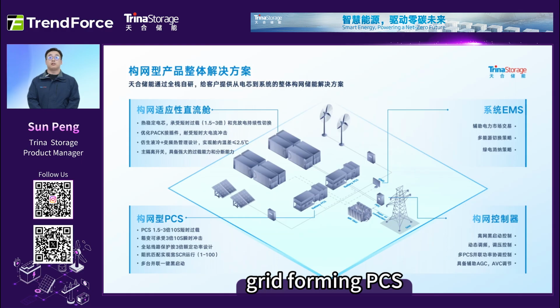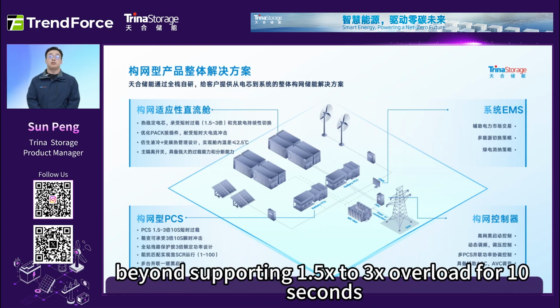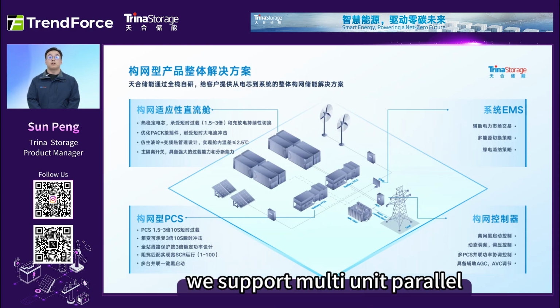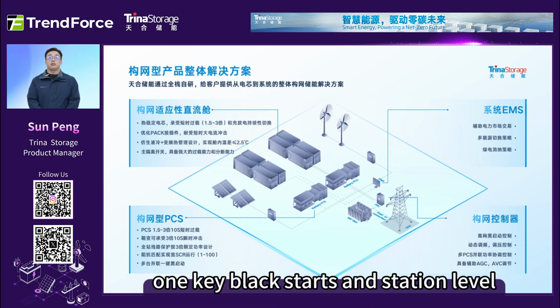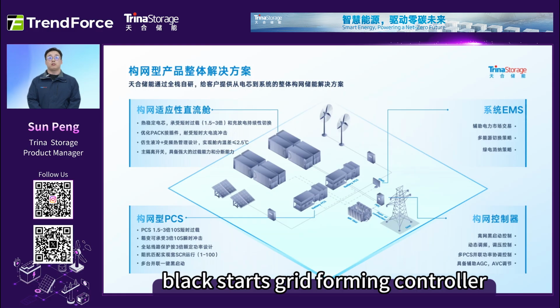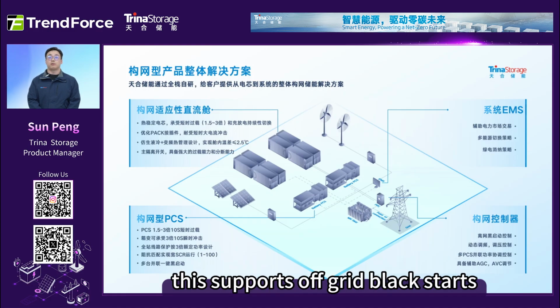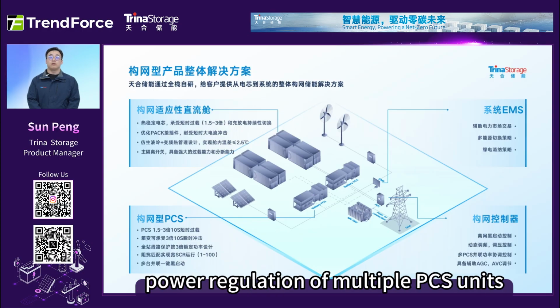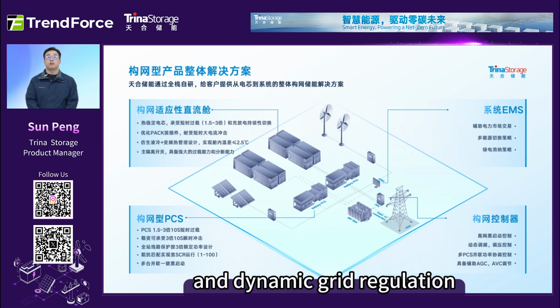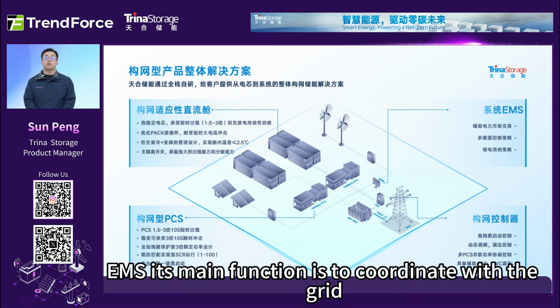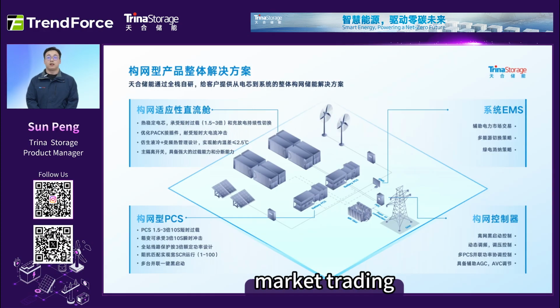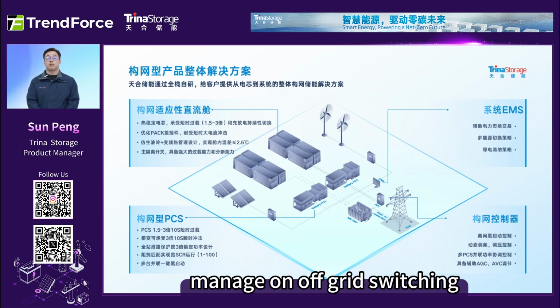Grid forming PCS: beyond supporting 1.5x to 3x overload for 10 seconds, we support multi-unit parallel 1-key black starts and station-level black starts. Grid forming controller: this supports off-grid black starts, power regulation of multiple PCS units, and dynamic grid regulation. EMS: its main function is to coordinate with the grid for electricity market trading, manage on, off-grid switching, and switch between operational strategies.